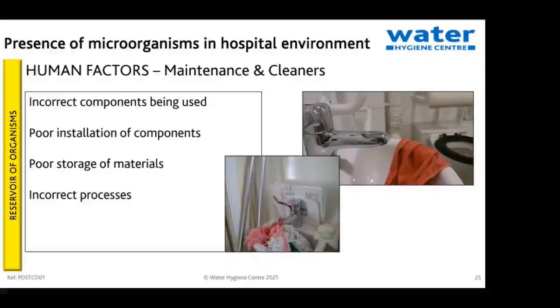What are some of the human factors that maintenance and cleaners introduce? Incorrect components being used, poor installation, poor storage of materials, and incorrect processes. For example, strainers not being cleaned leading to a build-up of biofilm and bacteria, dirty tools and components being used, and contamination from other sources - such as wash basins used to store dirty mop heads in contact with the tap end, a direct cross-contamination. Whatever's been on that floor and mopped up is now on the end of that tap. Cleaners also take the cleaning cloth from the waste aperture up to the end of the tap - direct cross-contamination, so what is at the plug as waste is now at the end of the tap.